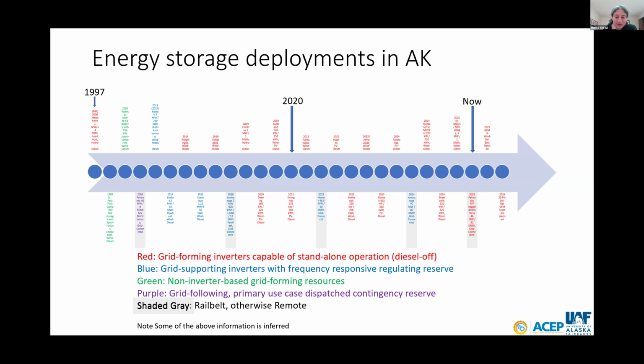Specifically, I know people talk about different categories of grid forming inverters. When we talk about grid forming inverters within the context of these remote microgrids, we definitely mean they have to be able to operate standalone. So it's not like grid forming plus or whatever. If you're going to send a grid forming inverter out to a remote microgrid, it better be able to generate the grid all by itself.